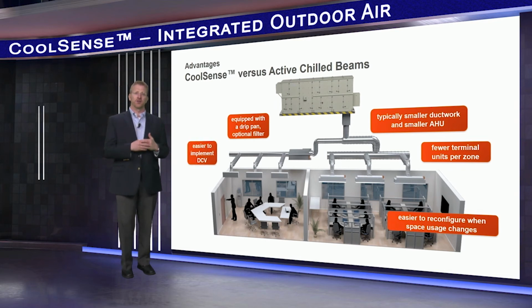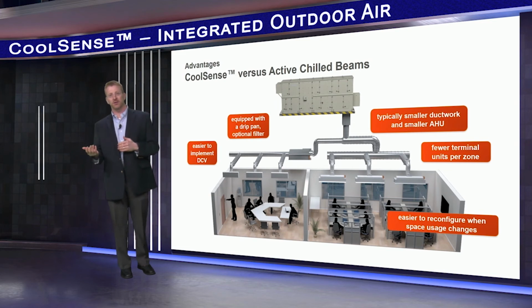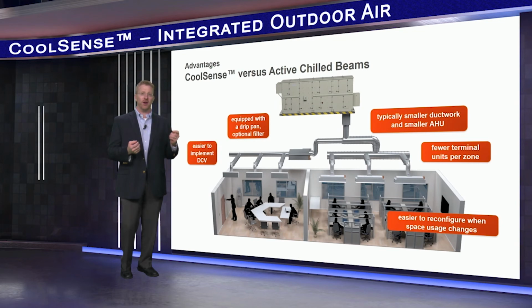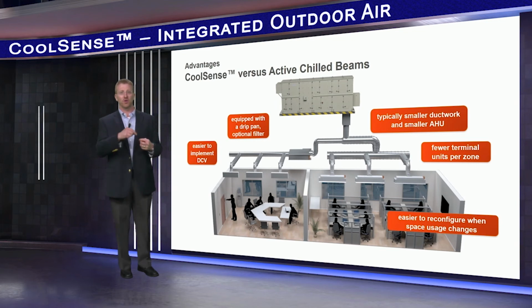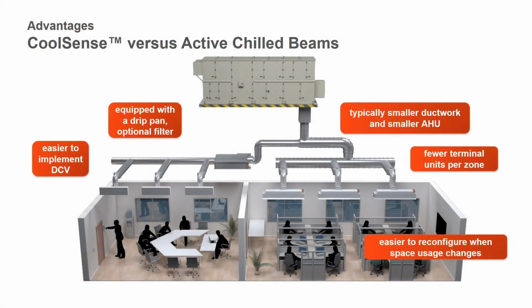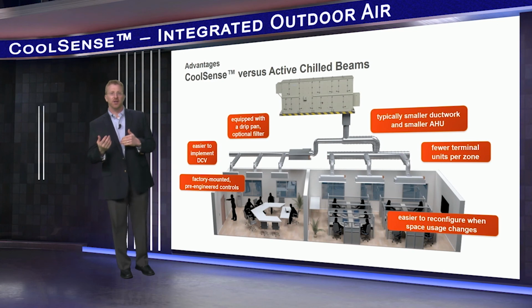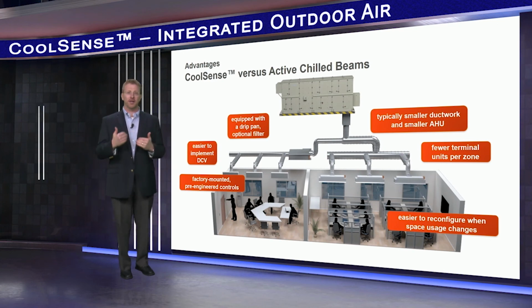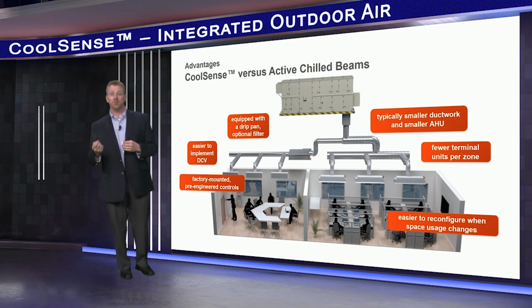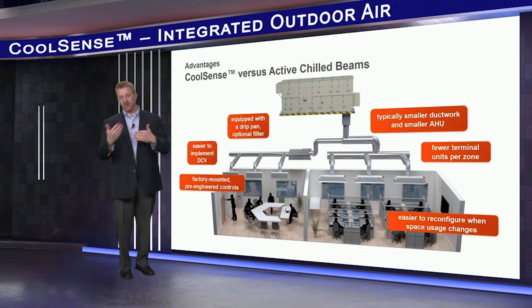Next, as we discussed earlier, it is easy to implement demand control ventilation, or DCV. After all, the CoolSense system integrates the outdoor air, meaning that 100% of the outdoor air is flow measured and integral to each zone level terminal unit, which makes demand control ventilation straightforward to implement. And as John mentioned, we've pre-engineered this into our controller along with overrides or boost to help if zone humidity gets too high. In contrast, in a chill beam installation, separate zone level dampers in the primary air ductwork are required to implement DCV, which adds costs and complexities.